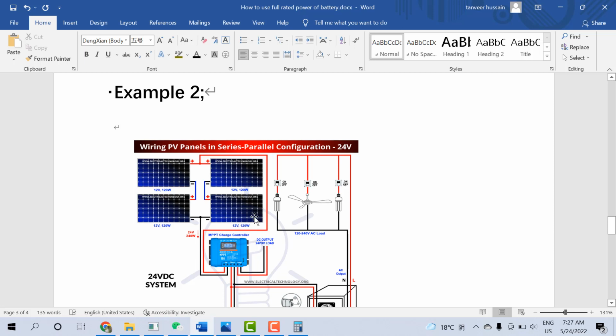The other reason is if you don't have a good enough cable that can carry high current. For example, each pair provides 6 amps, two pairs 12 amps. A 12 amp cable you can find easily. If you have more pairs, for example one or two more, it will go to 24 amperes. So a 24 amp cable you also can find. But if you add more and the current goes high - 30, 40, 50 amps - such a high quality cable might not be possible to find.